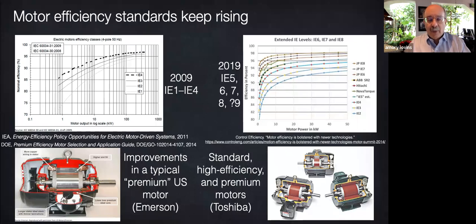The International Electrotechnical Commission, or IEC, standard called IE4, or super premium efficiency. IEC standards are observed in most of the industrialized world except the United States, which uses laxer NEMA standard, National Electrical Manufacturers Association. Now, the European Union requires at least IE4 for 75 to 200 kilowatt motors that are very common in industry, starting July 1st, 2023.